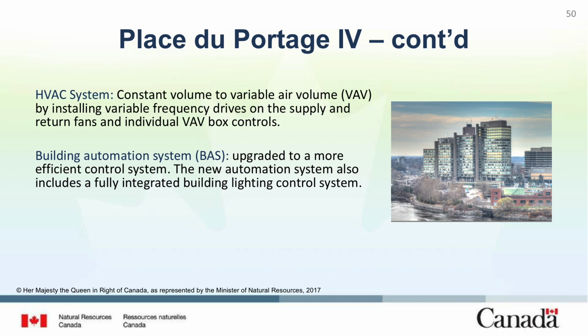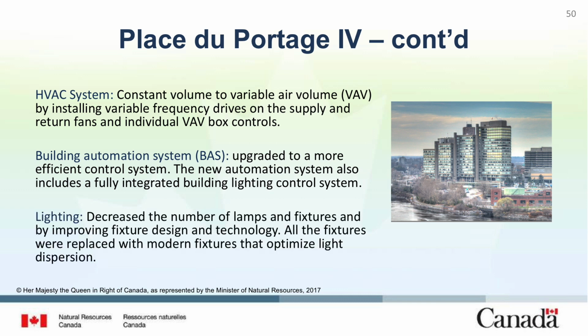The system's functionality was expanded, including extending BAS controls to the individual VAV box level and control upgrades to better utilize the facility's existing electric boilers. The new automation system also includes a fully integrated building lighting control system. Lighting retrofits achieved savings by decreasing the number of lamps and fixtures and by improving fixture design and technology.